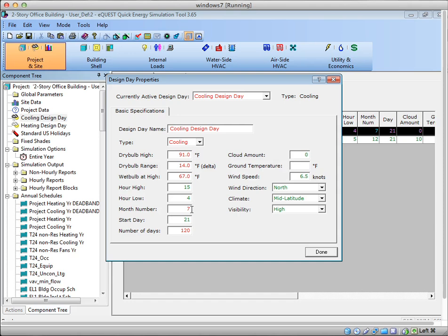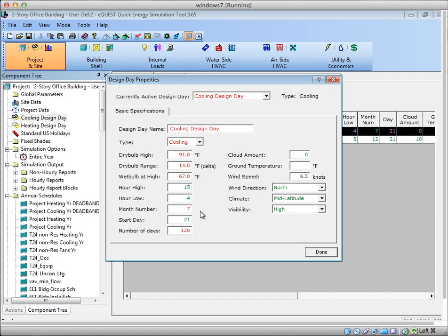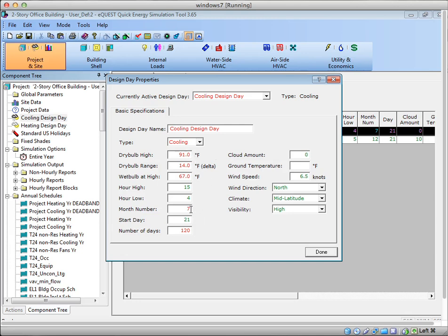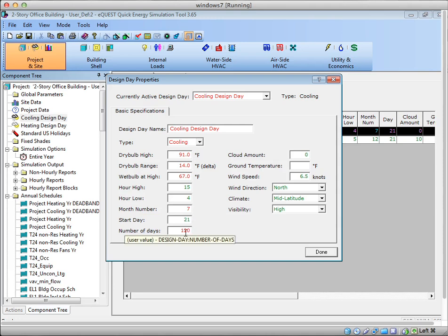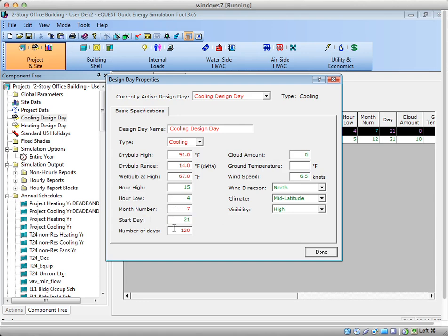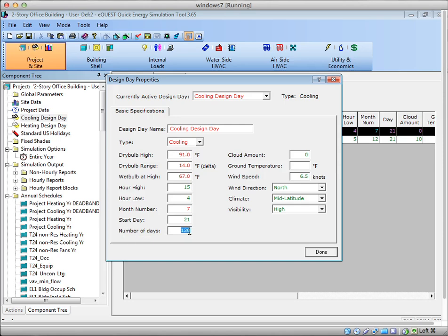The way I understand it is that eQuest will look for the hottest day, which is a combination of the dry bulb and the sun's intensity, and it will start on the seventh month, because that's what I've specified, and it'll start looking on the 21st day. And it's actually going to look for 120 days. Again, this is a value I specified. For this project, I sort of knew it would be the fall, and I didn't quite know when in the fall. So I said, well, let's start on the seventh month and just hunt over the period of 120 days.